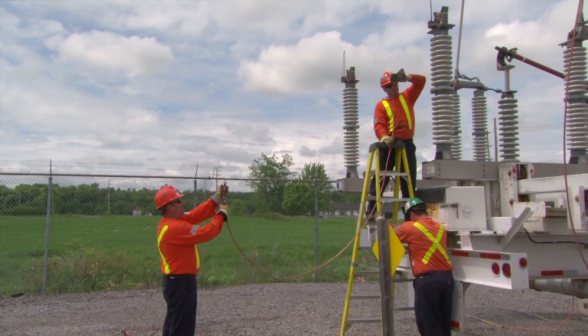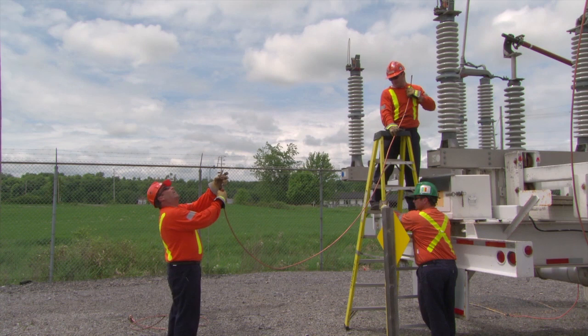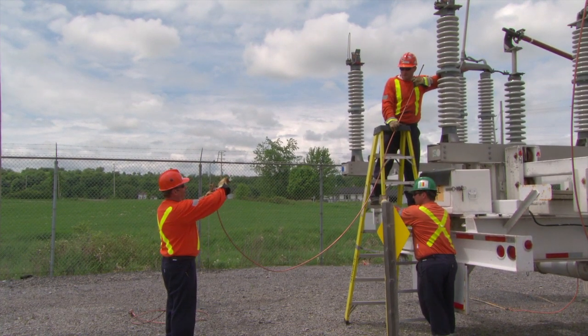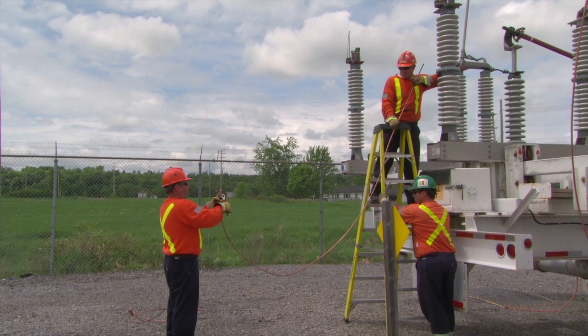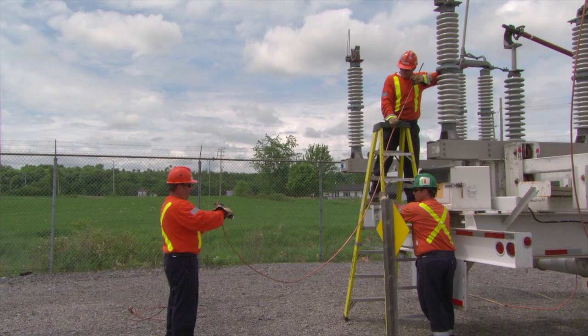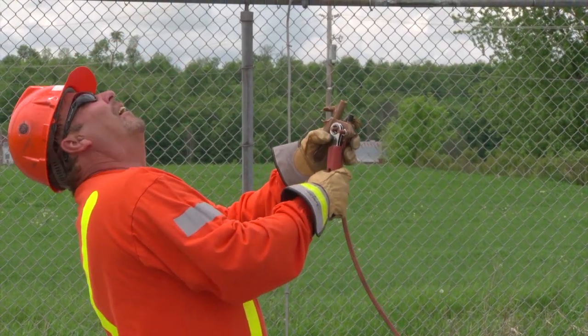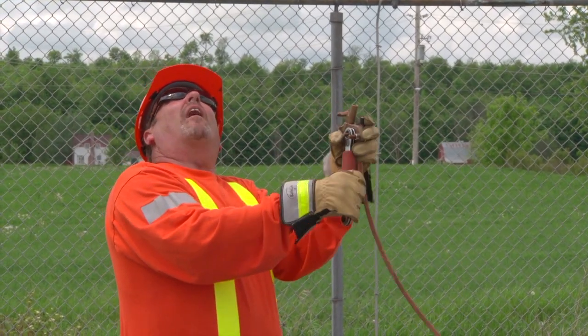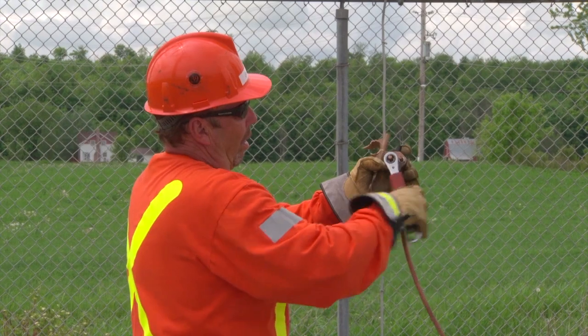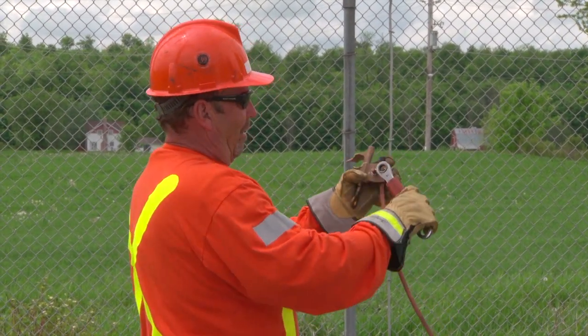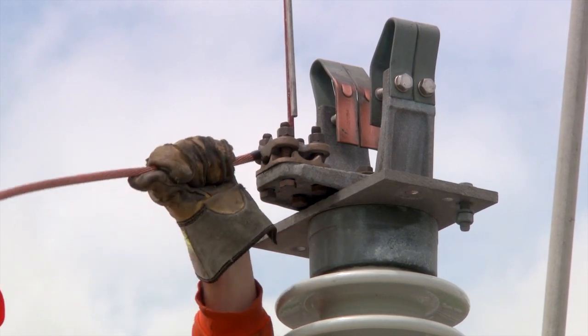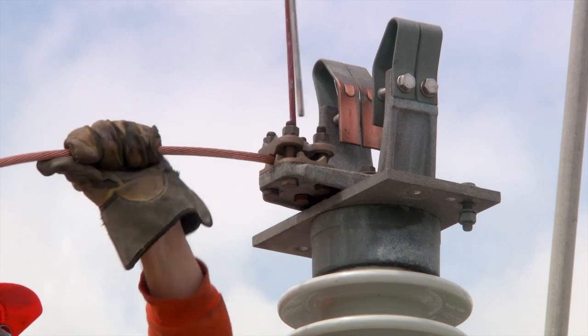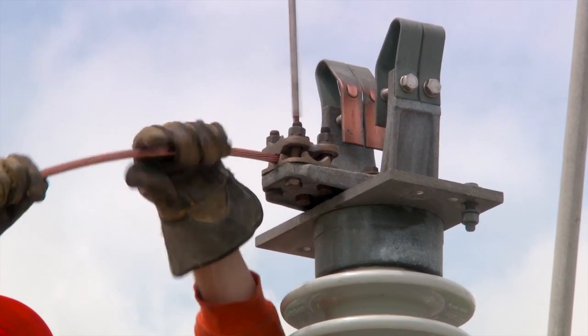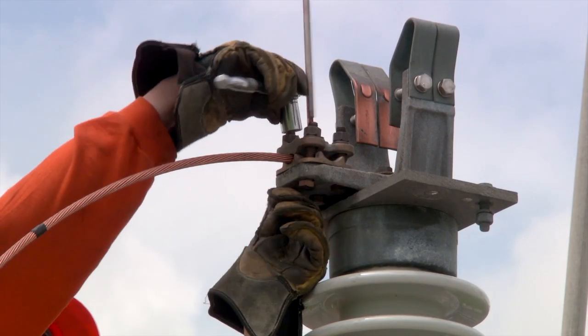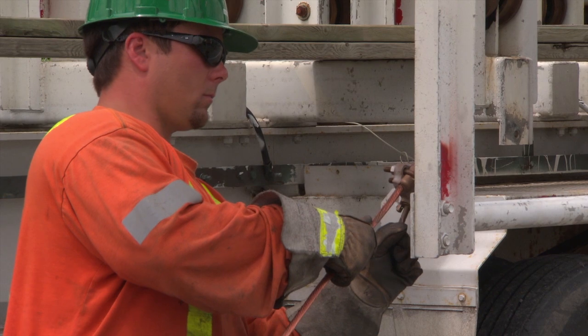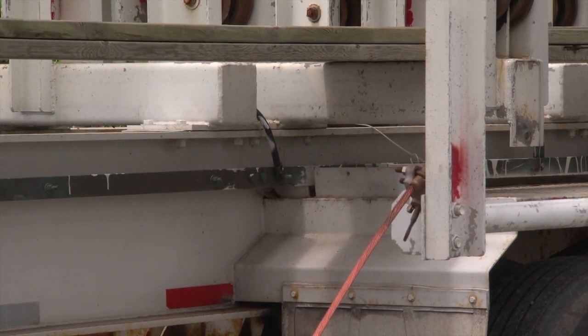Install live line connectors on the structure end of the leads. Take some time to align the live line connector to the stirrup it's going on. This will prevent torque on the conductor, making it easier to install and remove. Insert each conductor into the high-voltage pads on the switch jaw. Verify the orientation of the clamp before tightening the connector pads. The ends of the leads need to be controlled at all times to ensure they don't swing into live conductors or become a falling hazard to anyone.